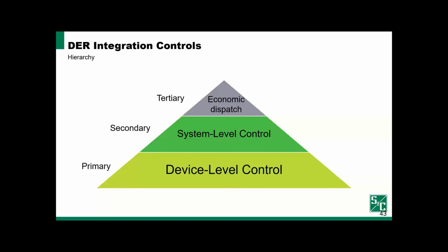At the lowest level, we have device level controls. We call this the primary level quite commonly. These device level controls include the inverter local controls, which will decide how to gate the inverter and switch it to produce a commanded amount of power at any given time. It also includes generator governors and exciters, and protective devices also fall into this primary control. These are devices that are using local measurements to make decisions primarily, and can make these decisions on the order of microseconds or milliseconds.